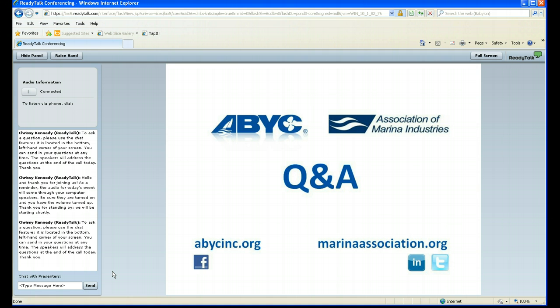Gary, in the work that you've done, have you seen a land-based installation being affected by a neighboring marina? I have not. Generally, current wants to go back to its source. So with a swimming area that's significantly away, and I agree with Chris that 300 feet may not be enough, generally the current's going to go back to its source, which is the shore power, and generally it's going to go back to the grounding system if there's a leak in the water. And if the marina is made of metal, and if the adjacent boat hulls are grounded properly, that current leakage is going to go back to the marina itself. But there is the chance that a close swimming area could be affected.